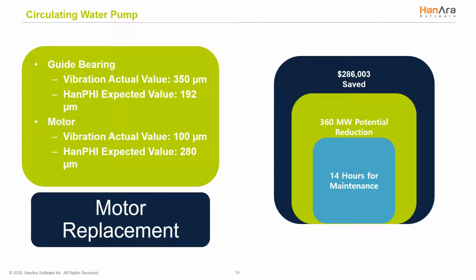After checking the vibrations weekly, the site utilized HanPHI to determine a steady vibration increase in April. The site prepared a spare motor to replace the motor in case the vibration rose to a certain level and planned motor replacement over the next month's overhaul. With HanPHI, the plant prioritized maintenance and planned for future overhauls.